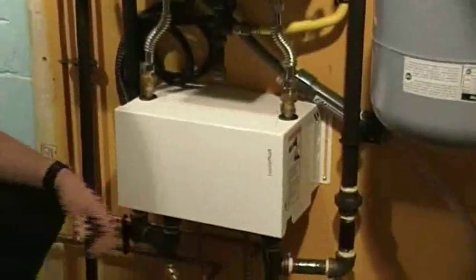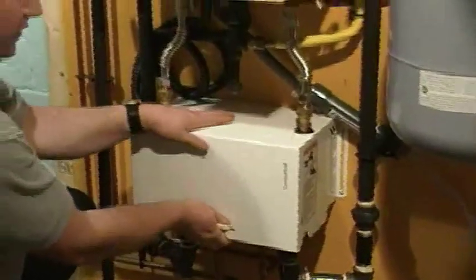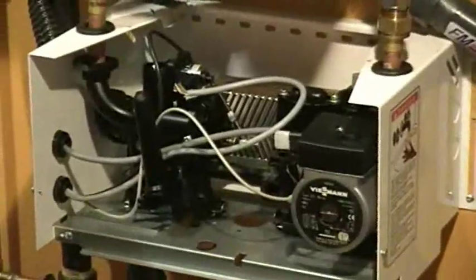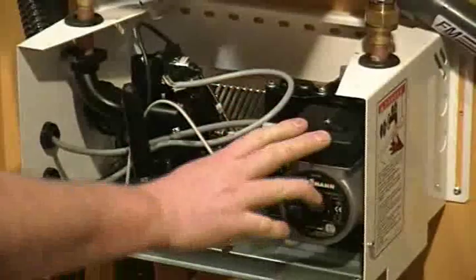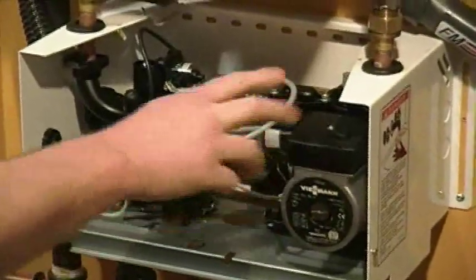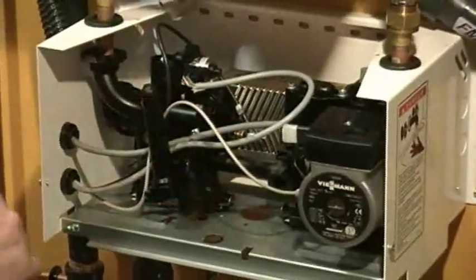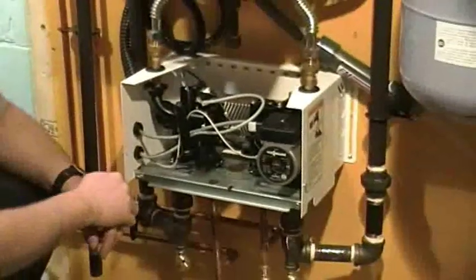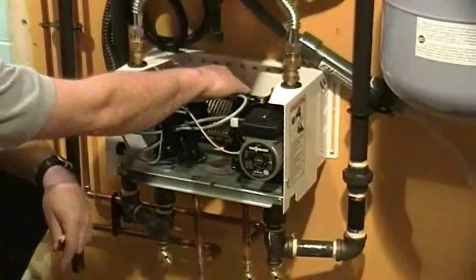On the Combi-PLUS, I'm going to open it up and show you guys what's inside of here. It's a very simple unit. It's easy to service. It's a very unique design. Basically what we've got is a pump which now acts as our primary pump for our primary loop around the boiler. It also drives water through the boiler to make domestic production. We have a stainless steel heat exchanger that is part of this.